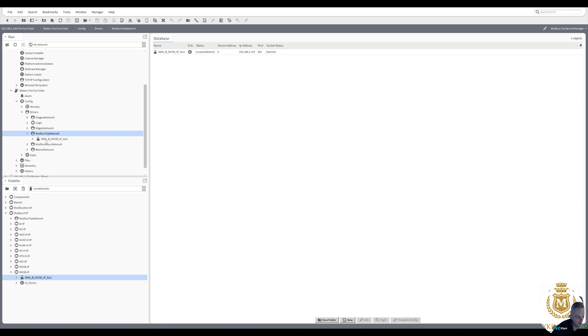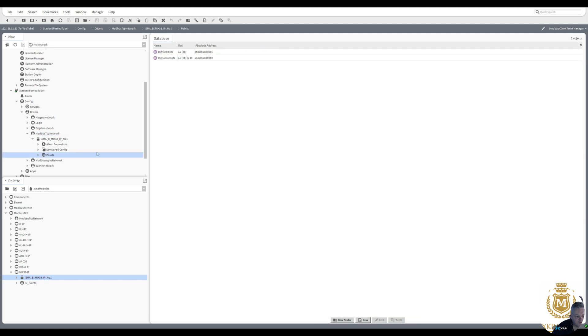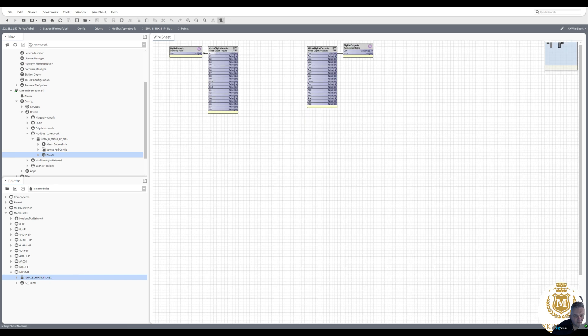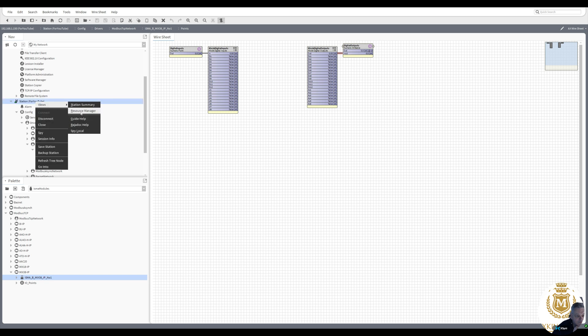The reason I added this is just to show you that if I used all the inputs on this device, including the universals as digital, I would have 20 digital points but only using one proxy. Then if I use the 12 digital outputs, that's again only one proxy point. And if I use the six analog outputs with 10V DC or 6V DC relays, I could control those outputs — so literally 38 IO but only taking the space of two IO.